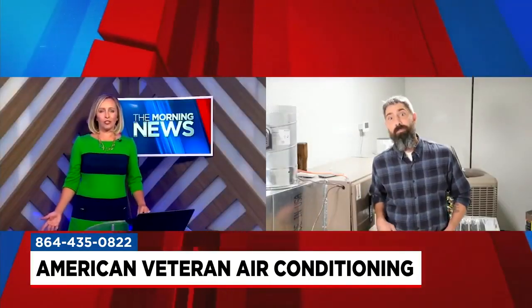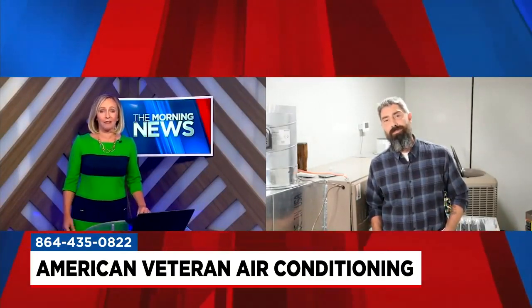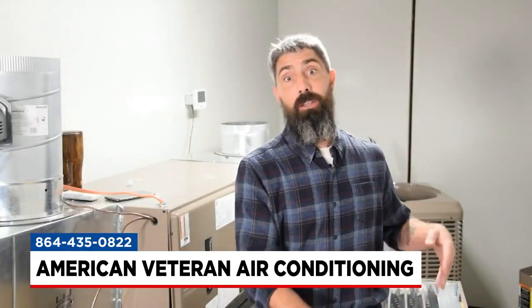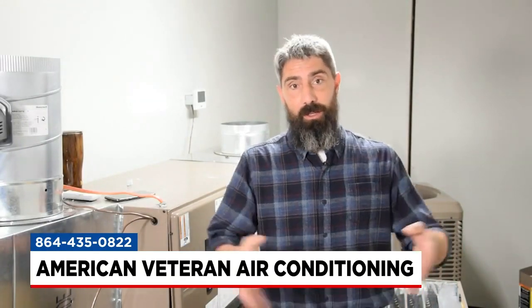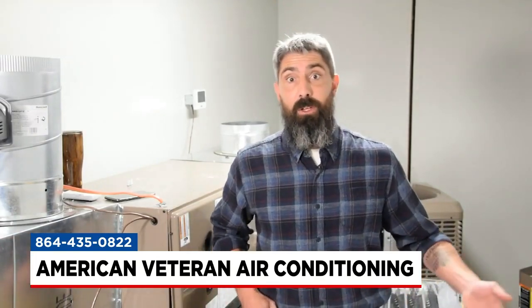And you also say a homeowner should not ignore their ducts because the home loses a lot of energy if there are leaks. How much do ducts affect our systems? If they're undersized, they affect it a lot because now you're not getting that airflow across the system. So now you're looking at high temp rises on the heat exchangers, and that constant contraction and expansion causes them to crack and fail.